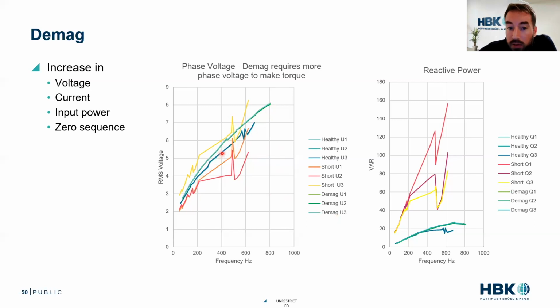So if you want to track what leads up to a fault, you can absolutely do a little machine learning and follow long-term averages to track things like failures. Because while the short circuit is quite dramatic, the more realistic scenario of demagnetization is a lot more subtle. We can see that in our reactive power. Once we get to a certain frequency, we can see in this demagnetized case a very subtle shift at a higher frequency.